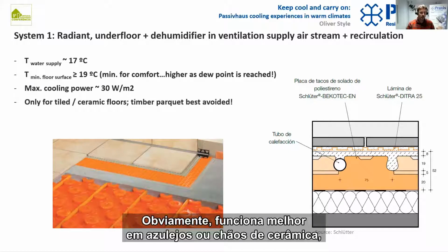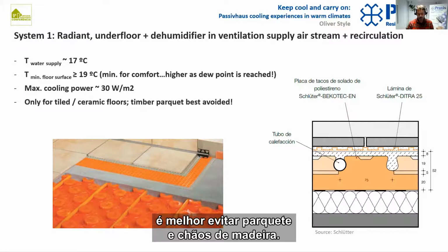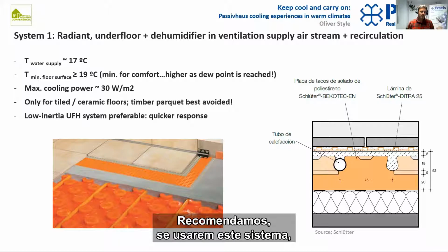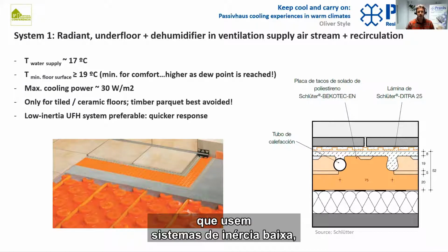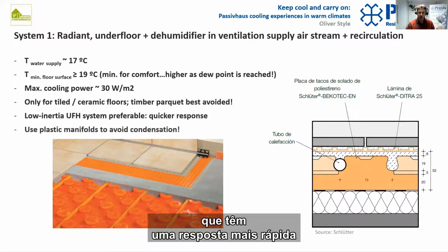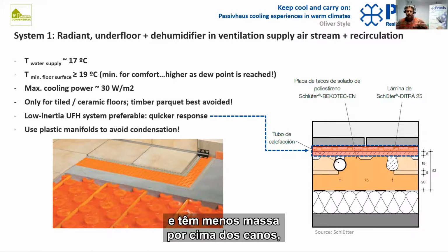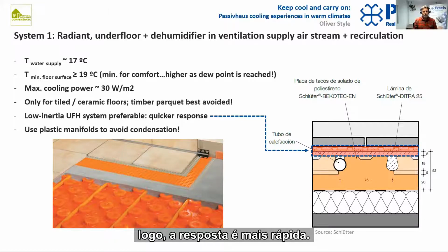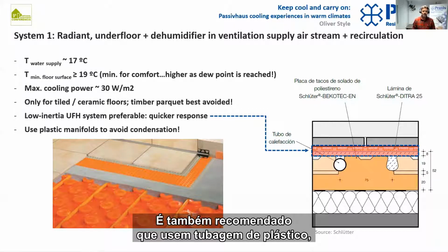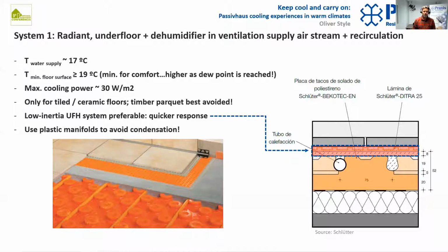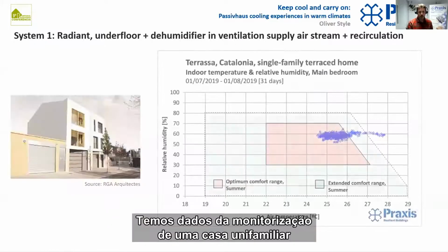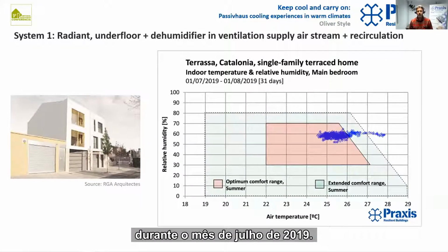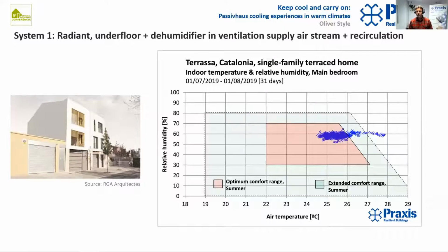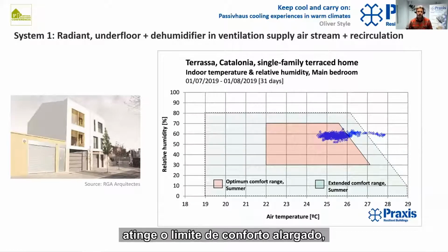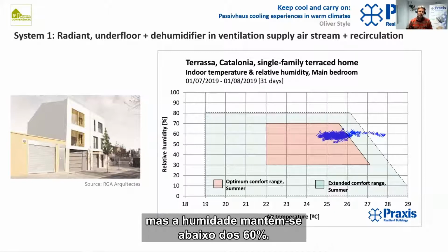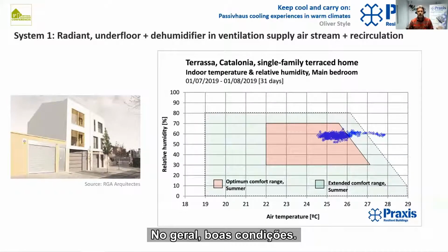Obviously, it's best on tiled or ceramic floors, better to avoid parquet timber floors. We recommend, if you do use underfloor cooling, to use low inertia systems, which have a quicker response and have less mortar, less mass above the pipe, so that they're quicker to respond. And also recommendable to use plastic manifolds to avoid condensation problems. So monitored data here from a terraced single-family home, you can see during a month in July 2019. So a few hours in which the air temperature moves into the extended comfort range, but pretty good humidity below 60%, and in general good conditions.